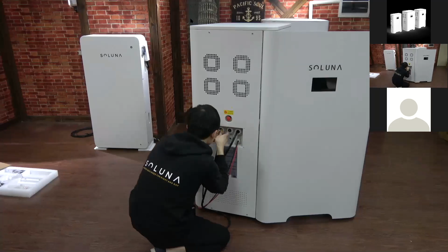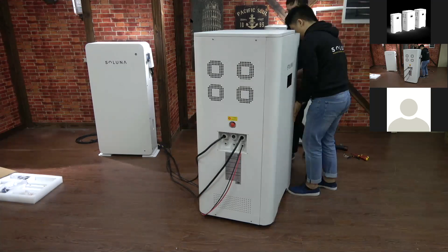One question is on the all-in-one string sizing for that system. Do you guys have a string sizing tool for the panels? You mean the maximum power for the solar panel? As we're stringing up solar panels into your system to be DC coupled, what does the string configuration look like? Right now our system can support 2 strings of solar panels, we have 2 MPPTs inside.